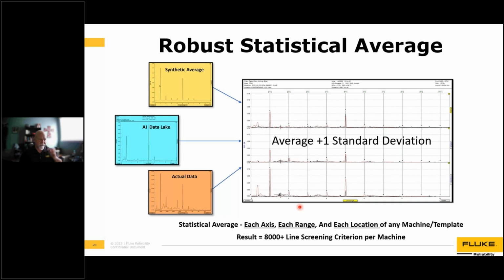Several years ago, I had a customer that had some vertical lube oil pumps that were shaking well over any vibration standard. They were nearly an inch per second at rotational rate of the motor. So immediately upon startup of this program, these machines were coming in and going out as a series because at 1 inch per second, that's significant levels of vibration.